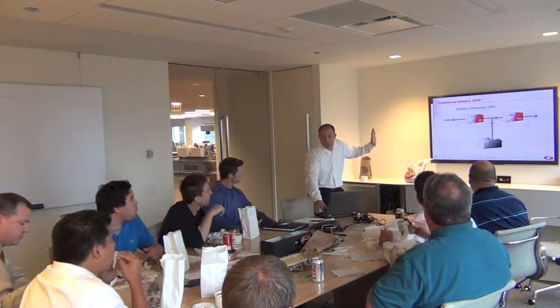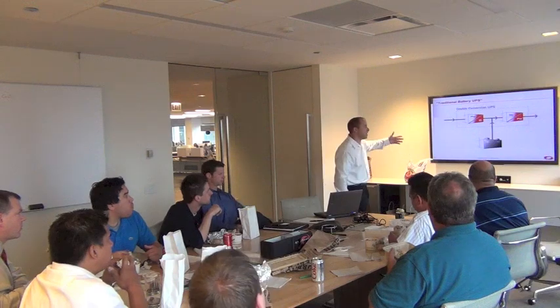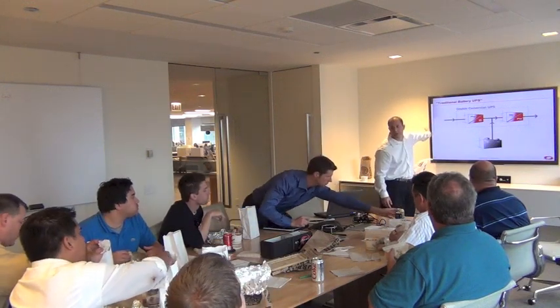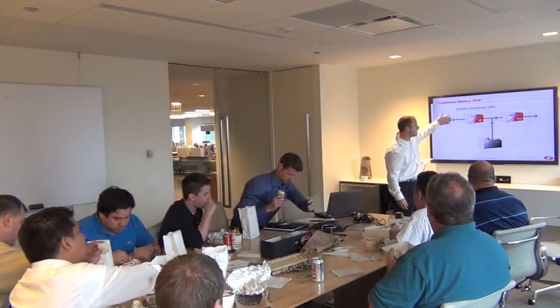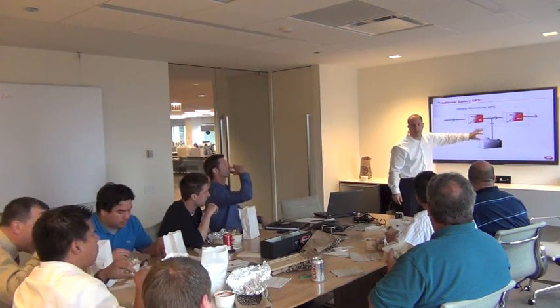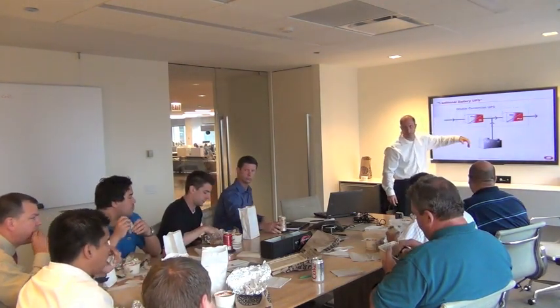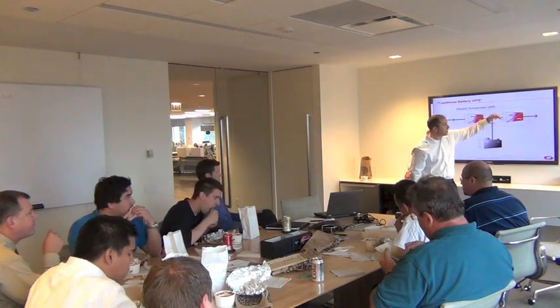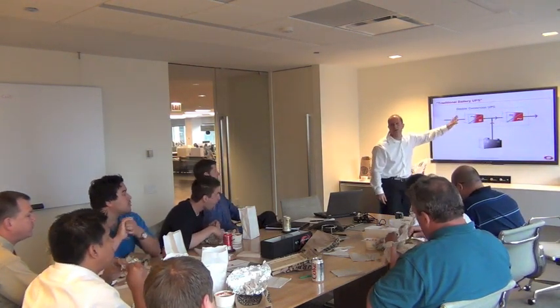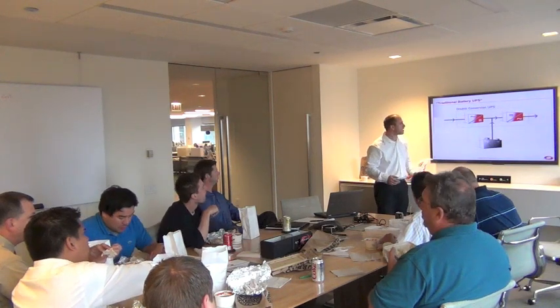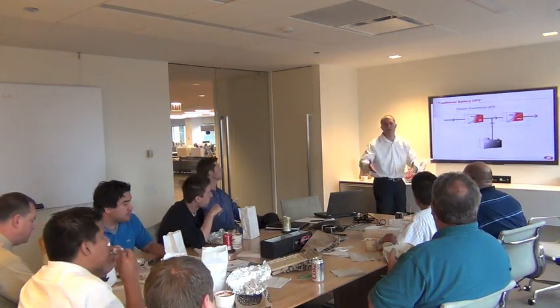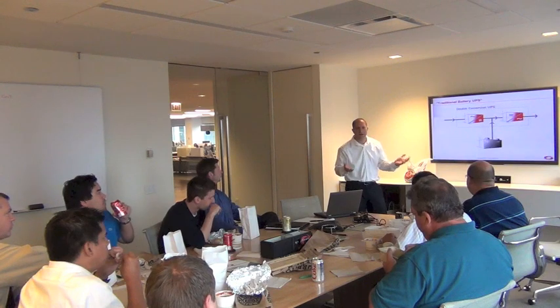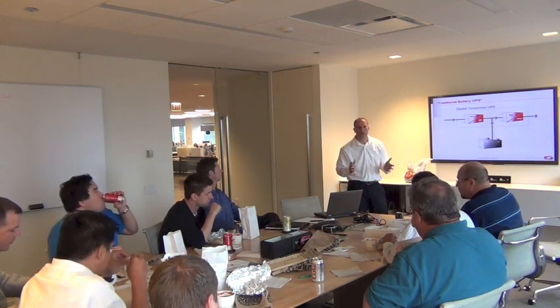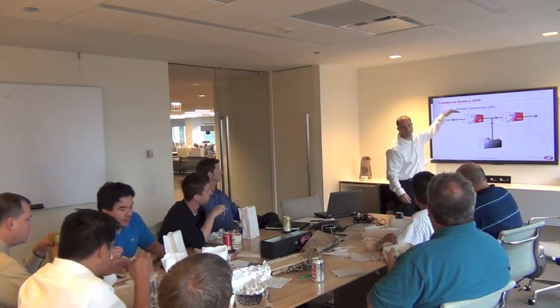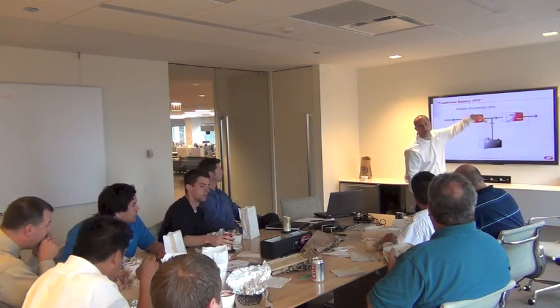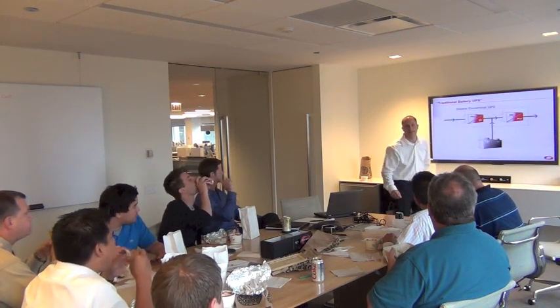You guys are familiar with traditional UPS topology, so I'm not going to spend a lot of time on it. You come in, your utility, 100% of your power is AC. You convert it to DC. Off your DC bus is where your energy storage is, VRLA batteries or wet cells. And then you convert from DC back to AC to your load. So most traditional double conversion UPSs, they're getting better, but on average now, if you look at the 9395 or Liebert, they're typically about 93, 94% efficiency at best. And most of the losses are obviously in this conversion process, taking 100% of your utility, converting it from AC to DC, and then back to AC.